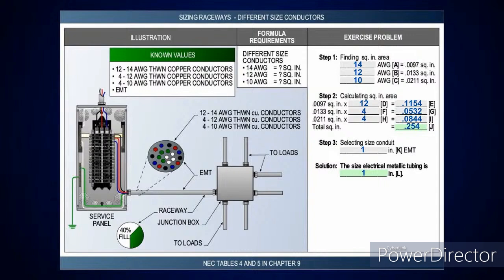Looking at this one with different-size conductors — I've got 12 number 14s, 4 number 12s, and 4 number 10s going into that junction box. You're going to go look at Chapter 9, Table 5 to get the square inches. We went ahead and put the square inches here for you to follow along. So: 0.0097 square inches is a number 14 conductor, 0.0133 square inches is a number 12, and 0.0211 square inches is a number 10.